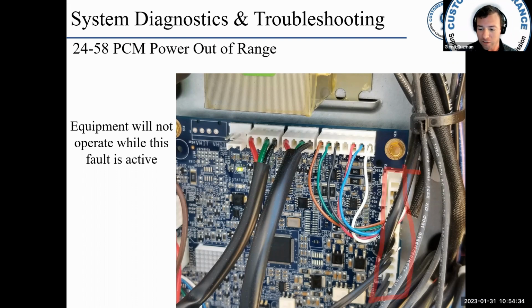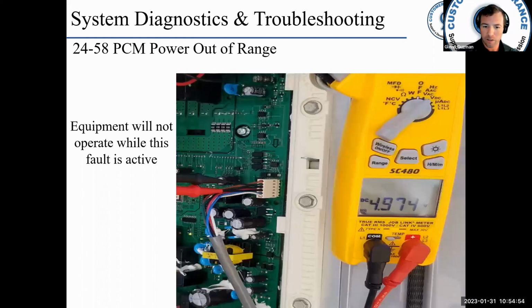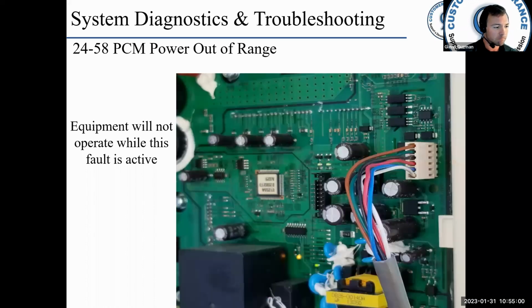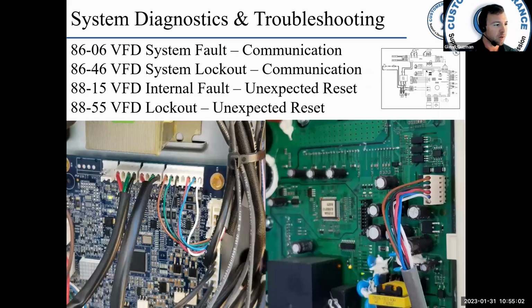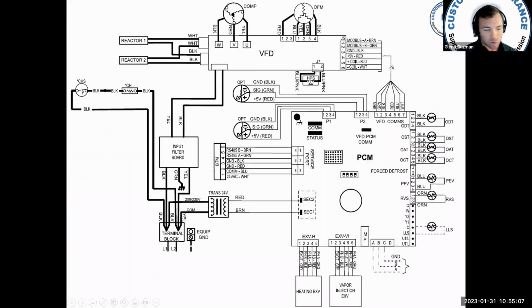If you have a shorted sensor, hopefully you would have a shorted sensor fault, okay? But you could have a shorted sensor dragging that DC voltage down and interrupting your communication between the VFD and the PCM, okay? So not too difficult, but you just gotta start with the process. Let's see if I get back to my wiring diagram here. So it might make a little more sense here if you're looking at this diagram.